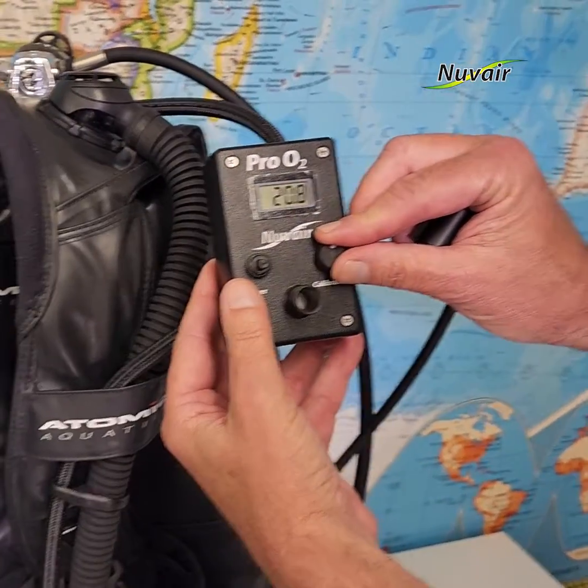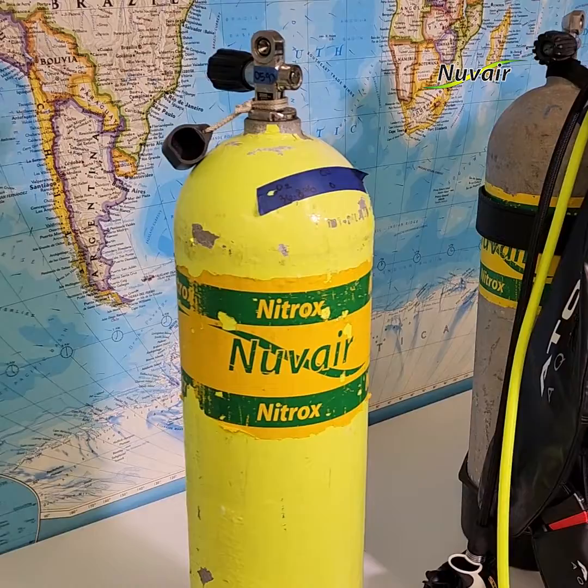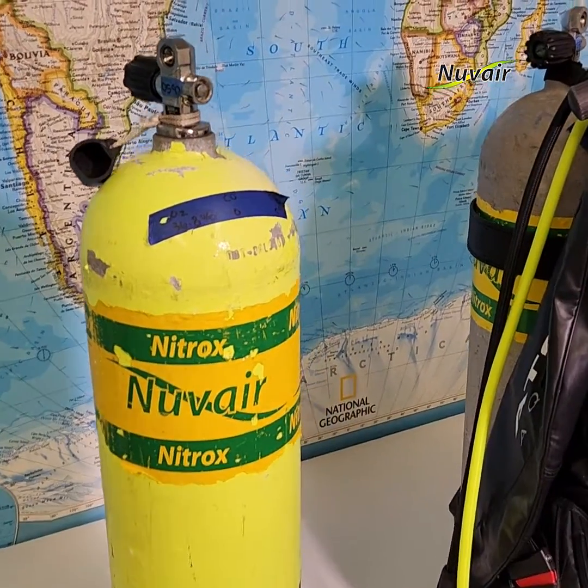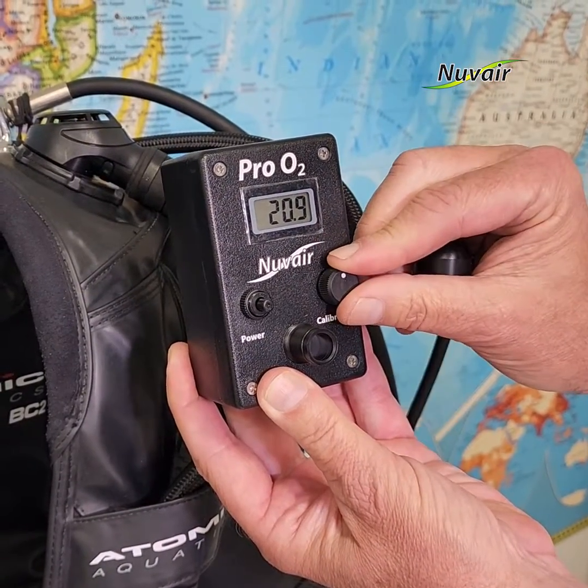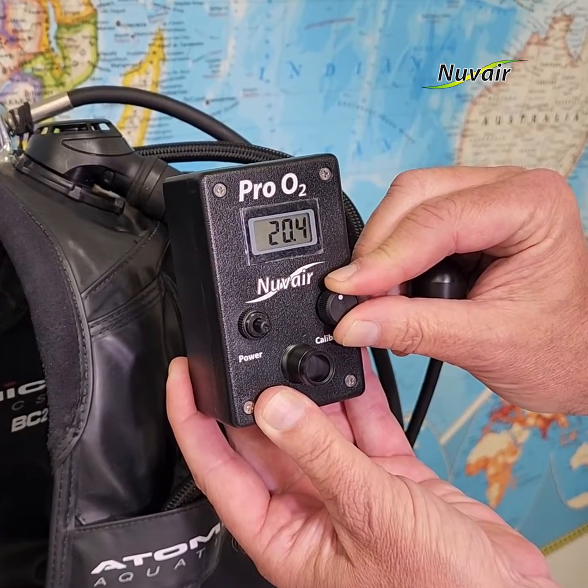The Nuvair Pro O2 analyzer measures oxygen levels in high-pressure cylinders, enclosed spaces, and compressors pumping enriched air nitrox in the range of 0.0 to 100% oxygen. The Pro O2 handheld is a water- and impact-resistant unit, compatible with outdoor and marine environments.